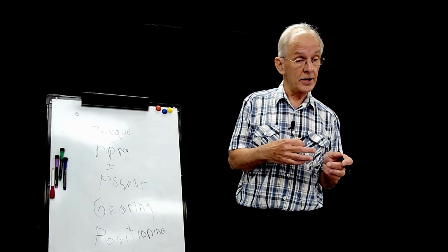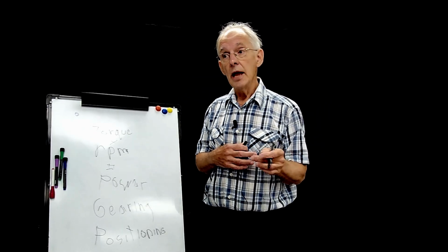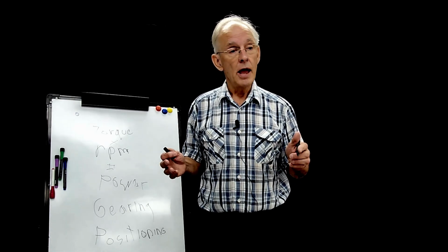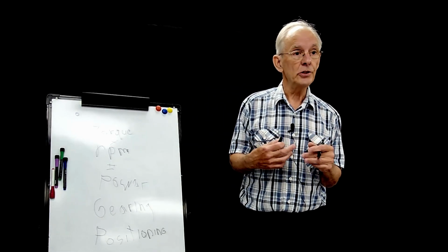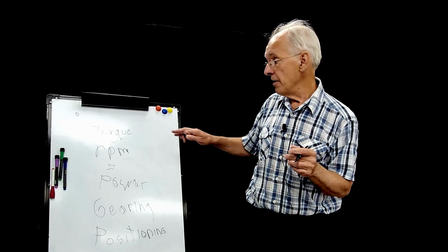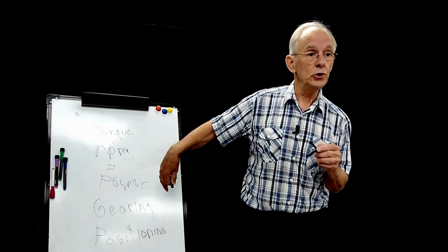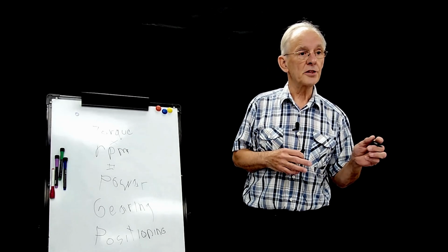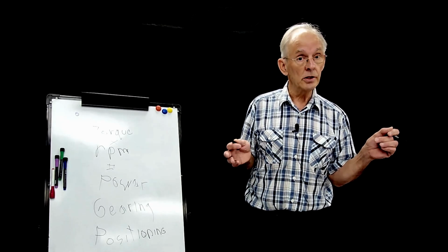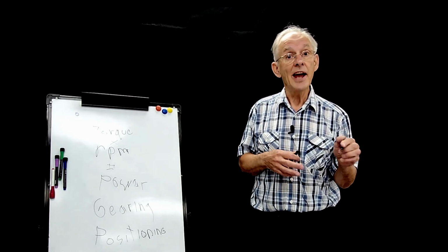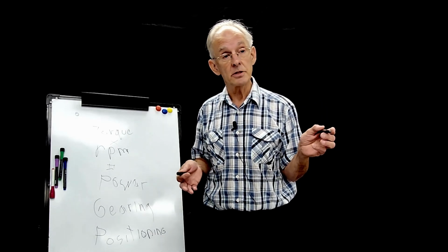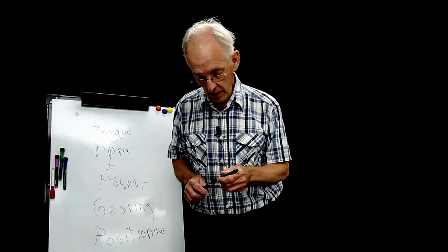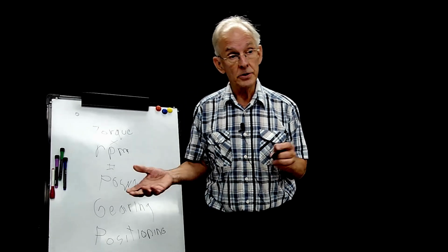One is you can add an encoder to the motor, and an encoder can be added literally to any motor. And the encoder gives you position feedback as a function of revolutions of the motor. So you might have an encoder that's 1,000 counts, which means that you can detect position down to 1,000th of the revolution of the motor. So encoders give you a way to do that.